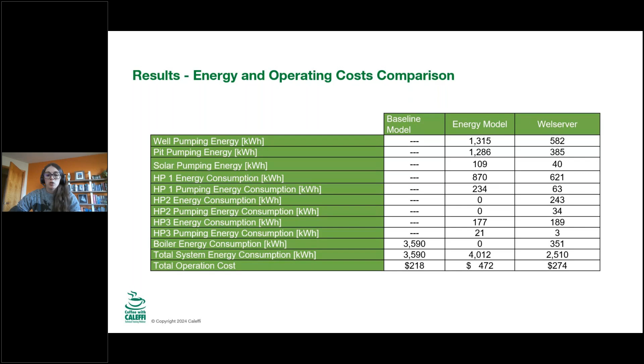The energy model overpredicted energy consumption by a factor of about 1.6, and overpredicted operating costs by a factor of about 1.7, during that measurement period from April to June. If that trend is applied to annual consumption, the combination ground source heat pump and solar thermal panels could save about 32,500 kilowatt hours per year and about $917 per year compared to a traditional propane boiler.